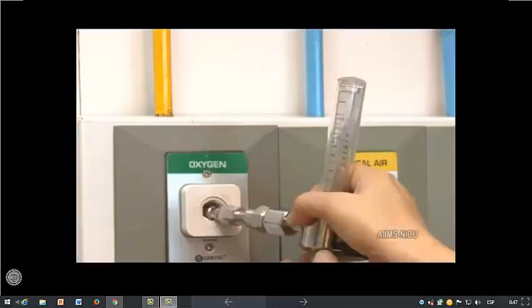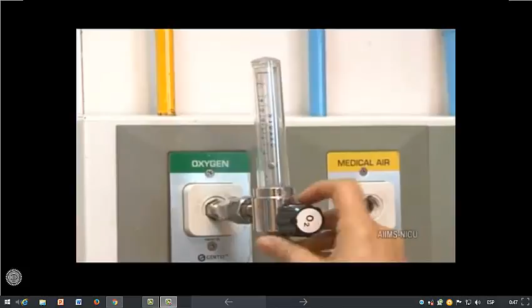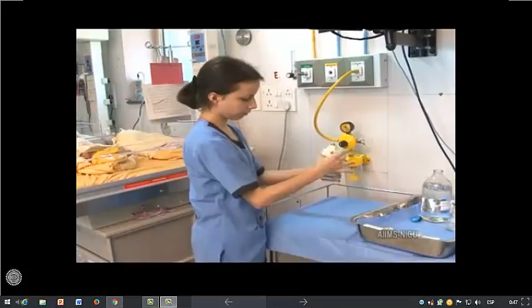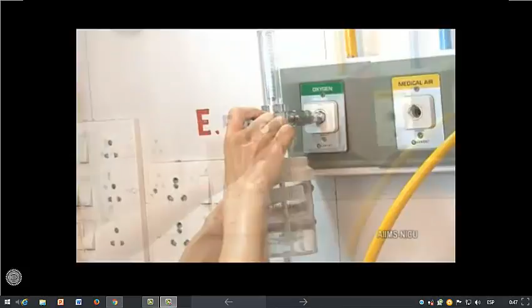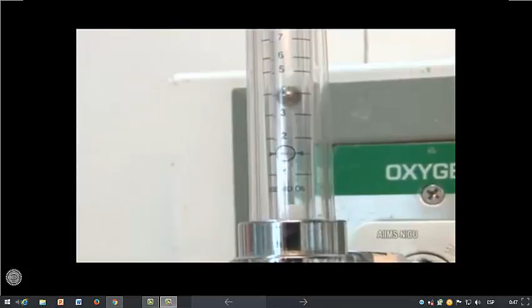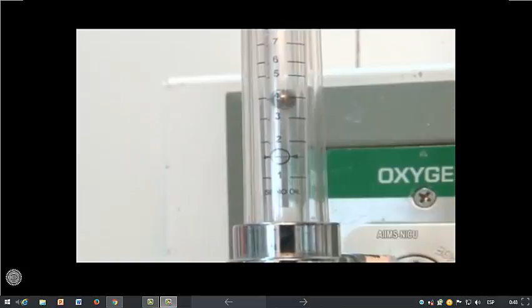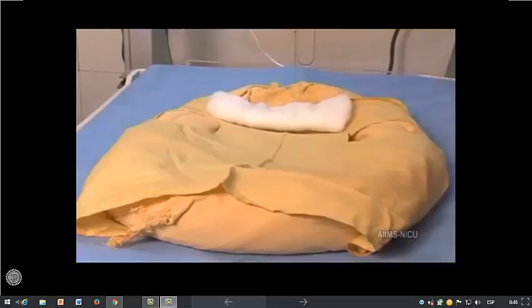Attach the oxygen tubing to the oxygen cylinder or to the central oxygen supply. Fill the humidifier with distilled water so that the oxygen delivered is humidified and not dry. Set the flow rate. Here, we shall learn about the administration of oxygen by hood. The flow rate is set at 3 to 5 liters per minute. Observe if the bubbles are coming out in the humidification chamber. Remember, the flow rate should generally not be less than 2 liters per minute while administering oxygen by hood. Now, position the baby's head in the midline and keep a shoulder roll to keep the neck slightly extended.